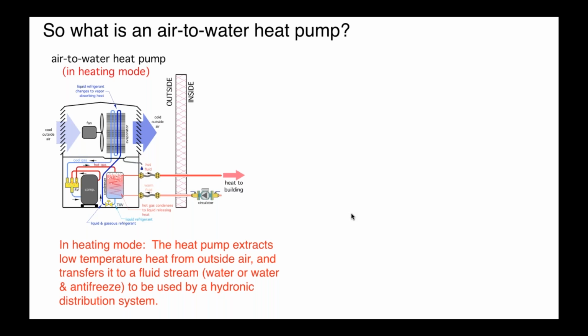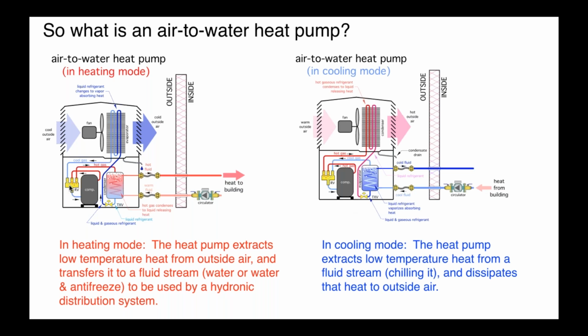I won't take the time to walk you through all the details, but basically it's the same thing that would happen in any other heat pump. Now, one of the components that you see here is a reversing valve. And all that does is it basically flips the function of the evaporator into condenser. In the cooling mode, that air coil is dumping heat to the outside air. We're dissipating heat. And the hydronic side of the heat pump is where the chilled water is being created, circulated back into the building. So basically, in winter, we produce a stream of warm water with the heat pump. In the summer, we produce a stream of chilled water.